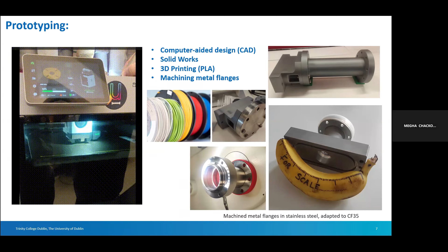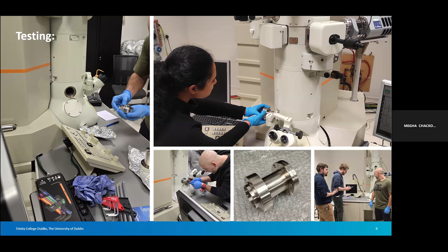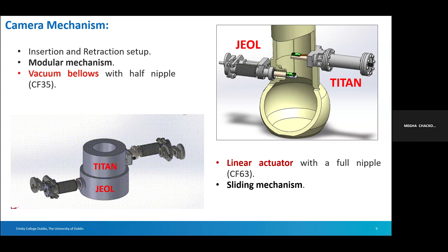The next part is testing, the most important part, where we have to make sure the vacuum condition is safe enough with these flanges. We have tested our machined flanges on the JEOL microscopes, and it is safe enough to go. As I have talked about the low cost, I'm also introducing a new insertion and retraction setup. If you have to use EELS spectroscopy or other detections while you are using the STEM, you can insert and retract the detector setup with a bellows or a full nipple design on these CF standard flanges.